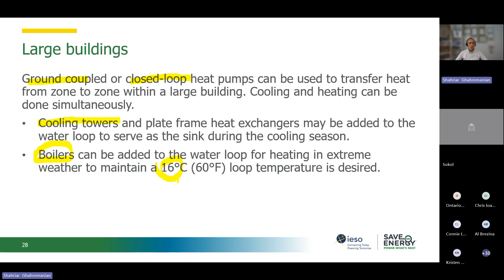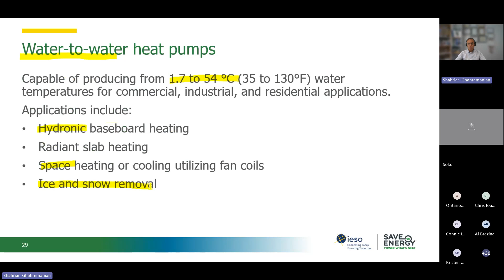So the water to water heat pumps are capable of producing water temperatures from 1.5, 1.7 to 54 degrees Celsius for any commercial, industrial, residential application, any of them. And the good thing is that we can connect them directly to the hydronic system that we have, or any radiant heating from the floor, or space heating using fan coils, or even the ice and snow removal that we want for our ramps or whatever. So these are good applications. I know that the capital cost is higher compared to the other systems, but again, it's good to be considered and evaluated for the projects that we are working on actually.